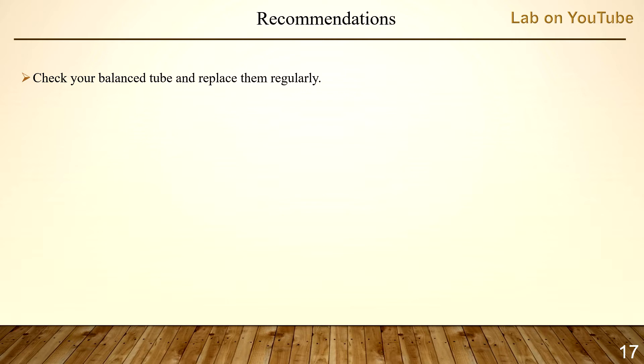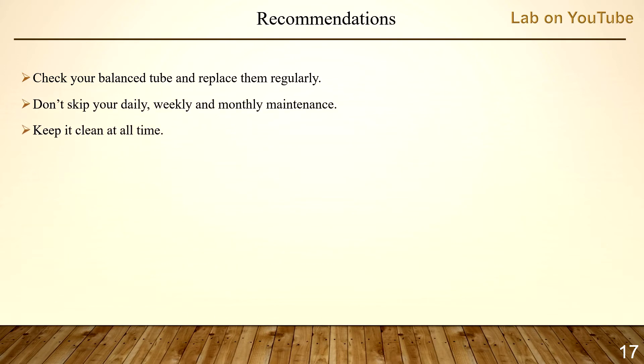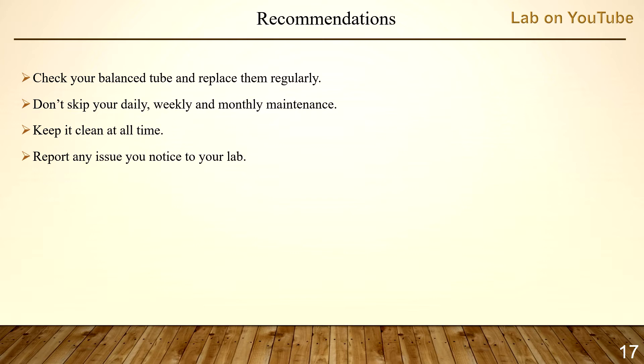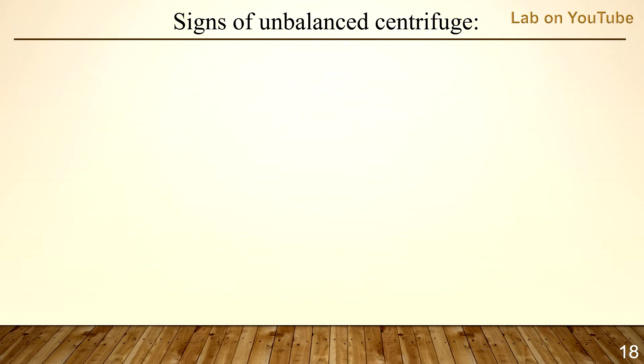Tubes have a certain limit for how many times they can be spun. Don't skip your daily, weekly, and monthly maintenance. Clean the centrifuge immediately after any splash or broken tube and keep it clean at all times, as it can be a source of contamination. Report any issues you notice to your lab. Signs of an imbalanced centrifuge include shaking, movement, or noise during centrifugation.